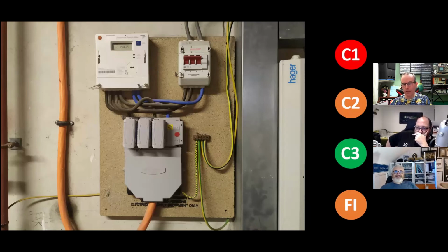Yeah, the lift, unfortunately, is one of these hydraulic jobs, which means when it goes up, all the weight of the lift is on the hydraulic thing, but when it comes down, there's pretty much no load at all because it's just under gravity. So not a particularly good thing, but it appears that whoever built the place assumed that three-phase was available, all the three-phase put in, and then it was only discovered when they were making the final connection in the street that, oh, actually, no, there's only two phases here. So, wow. So it's been lashed together with a phase converter.